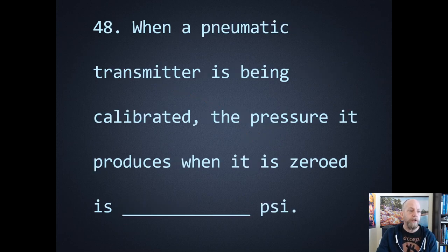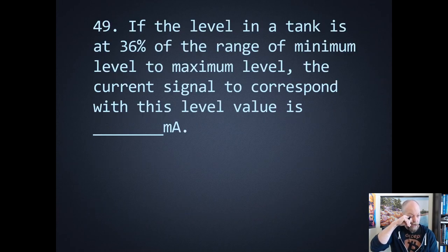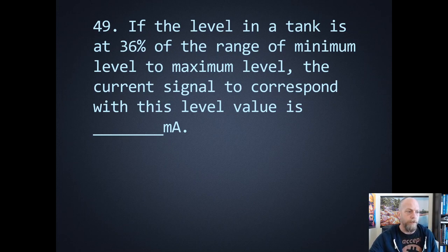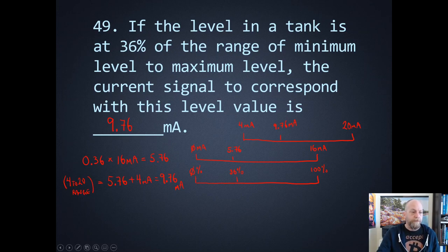Number forty-eight: when a pneumatic transmitter is being calibrated, the pressure produced when it's being zeroed — zero is the low end of the range. It's a 3 to 15 PSI range, so the low end is going to be 3 PSI. Number forty-nine: the level in a tank is at 36% of the range from minimum to maximum level. The current signal to correspond with this level is how many milliamps? The answer is 9.76 milliamps.